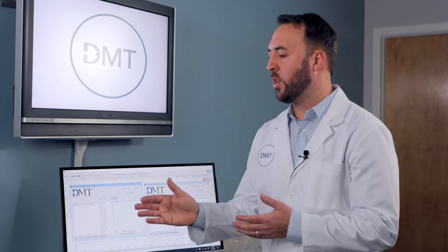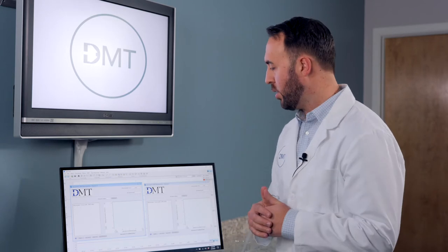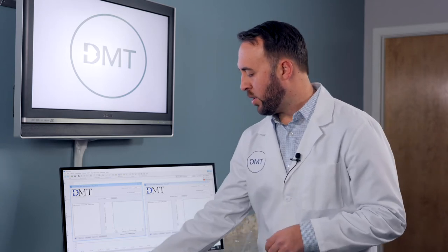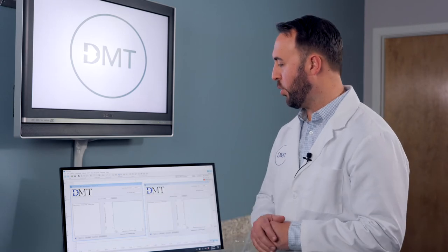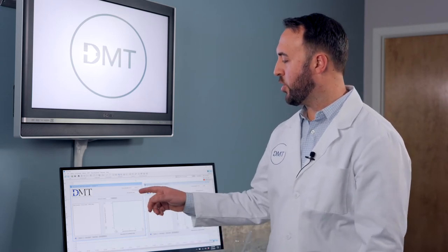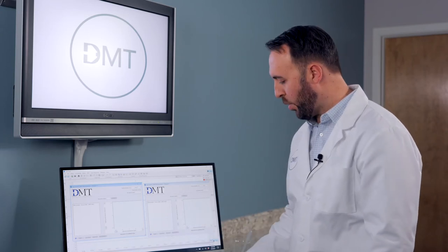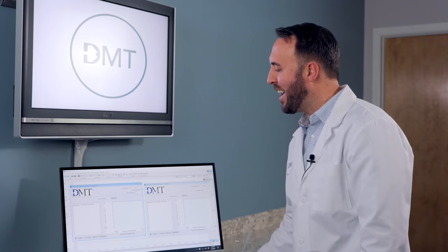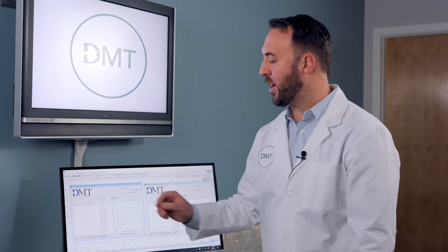So we saw in channel 1 that the vessel spanned the entire gap of the jaw. So we are going to set our tissue endpoints as 0 and 2. This will tell us that our tissue length is 2 millimeters, and we are using 40 micron diameter wire. And now we need to take a reading of the micrometer for channel 1. So we will take a reading.